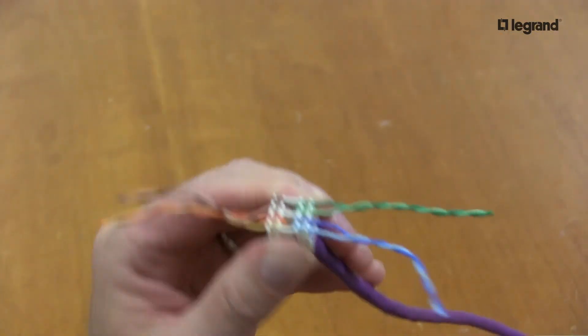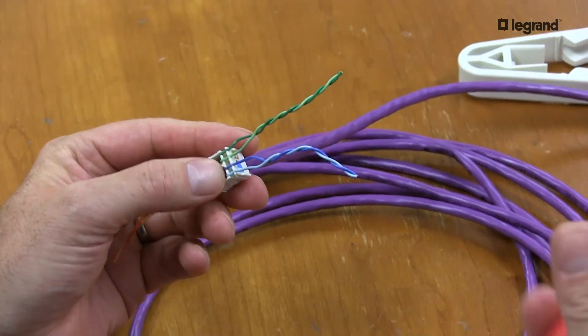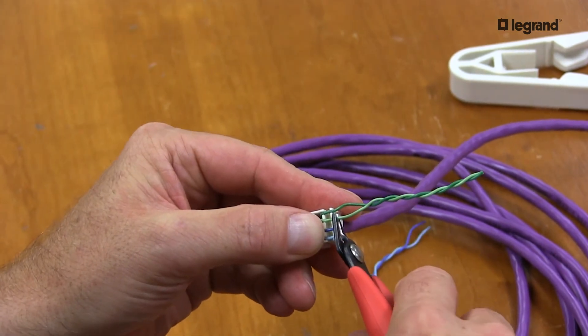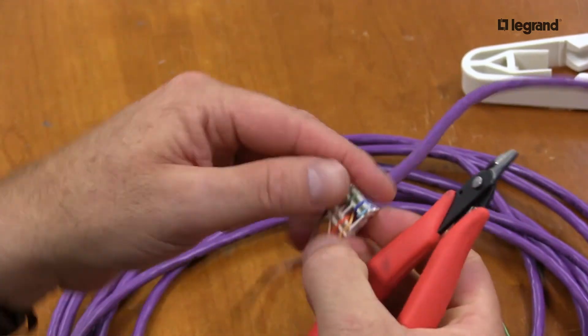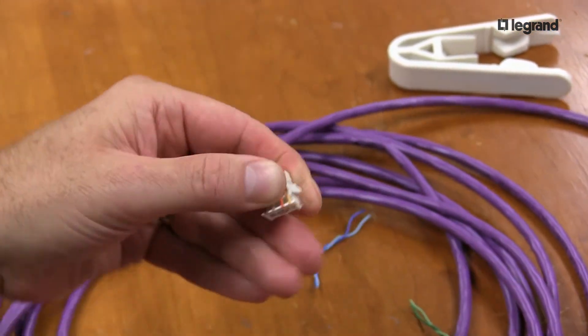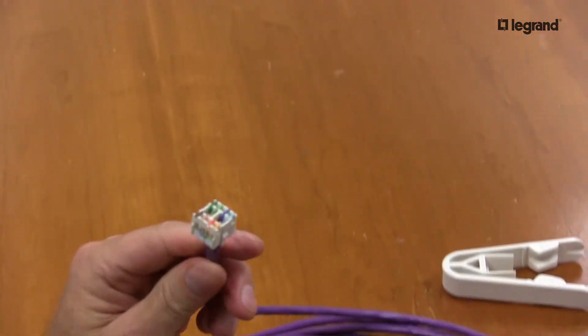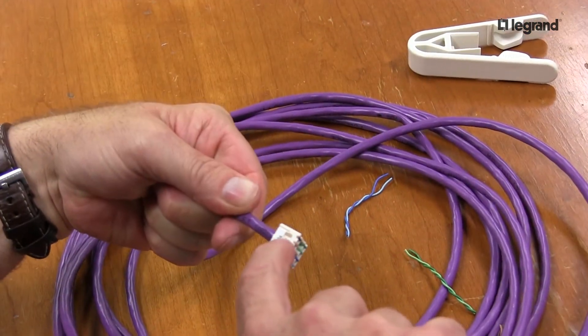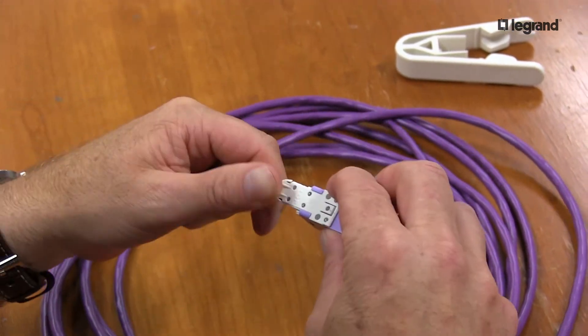White-blue, white-green, white-orange, white-brown. I like to use my angle cutters to get a nice trim right to the edge. Taking my time here so I can show you — notice all conductors are in all the grooves.